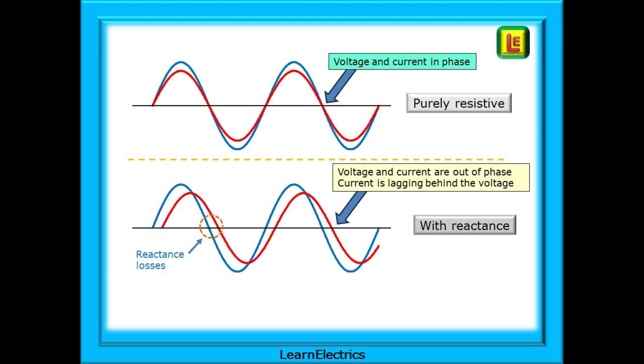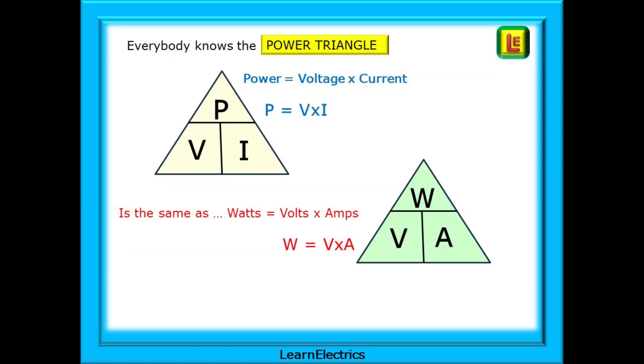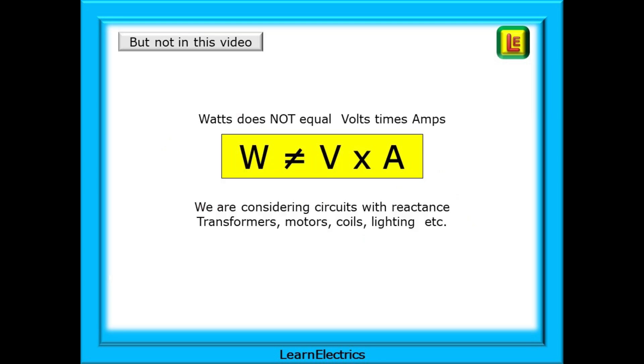This is why ZS, for example, is an impedance and not a resistance — it's a live test on the final circuit that has reactive equipment. Everybody knows the power triangle: power equals voltage times current, written as watts equals volts times amps, W = VA. But not in this video. Here, watts do not equal volts times amps. We are considering circuits with reactance — systems with transformers, motors, coils, lighting and so on.